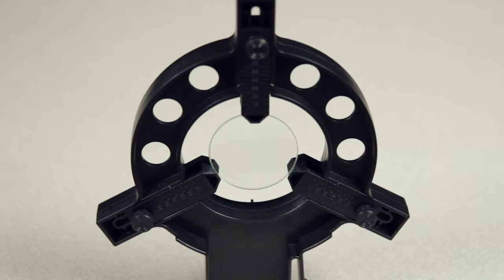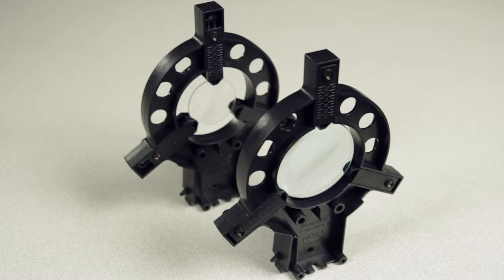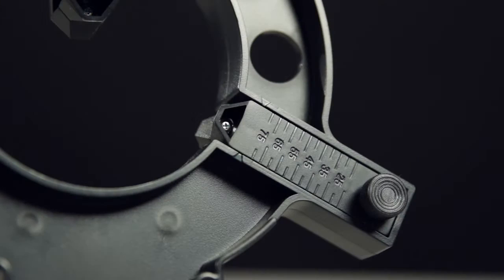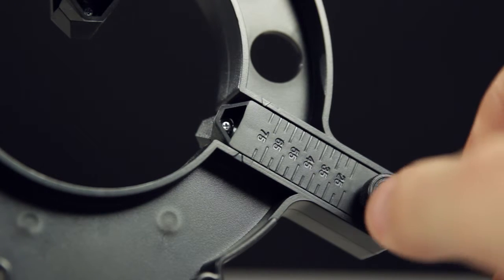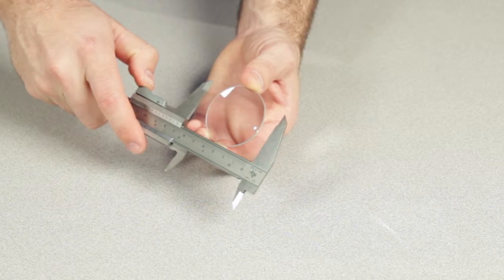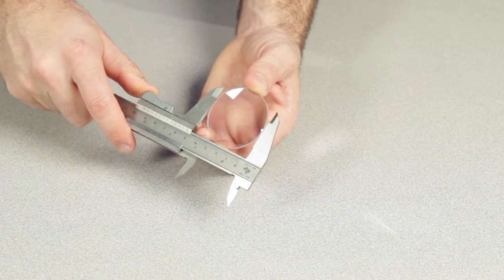The holder has three sliding arms that can be adjusted for different size optics components between 20 and 75 millimeters in diameter. Each arm is marked with a range of diameters in millimeters corresponding to the diameter of the component to be held. To mount a lens into the holder, first measure the diameter of the lens.